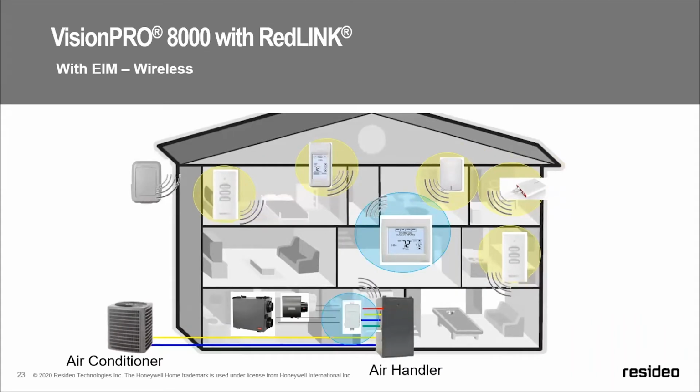So let's look at another scenario with an EIM. Okay, in this EIM, now we've added more and more possibilities. Like I told you, you can go up to those 3 heats, 2 cools, and in a light commercial application, 4 heats, 4 cools, but we can add multiple indoor air quality devices. And what's really nice there is you do all that wiring in one spot. You pull your wires off of your equipment, you bring in your humidifier, dehumidifier, and ventilator, all go right in there, done, that becomes the host. And then everything else that you want to add or subtract, you can go ahead and do that. What's really nice is you can actually sit in the utility room, do your wiring and set all your stuff, and then you take them out. No need to go out and hang the outdoor sensor and then have to run all the way back. You can carry it out there. It's really, really nice.